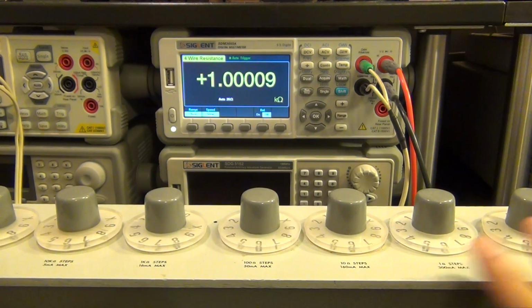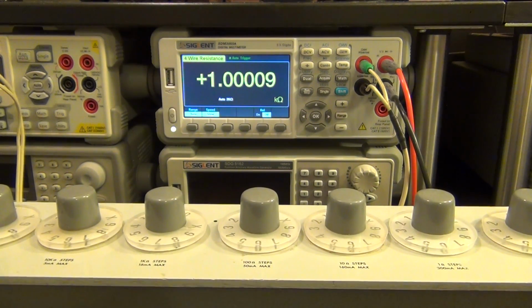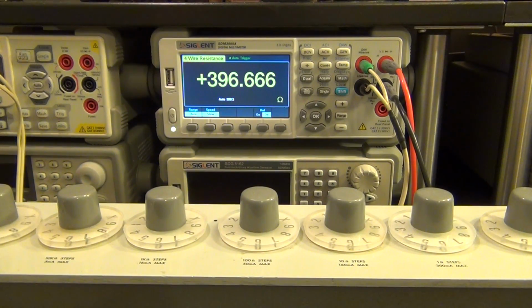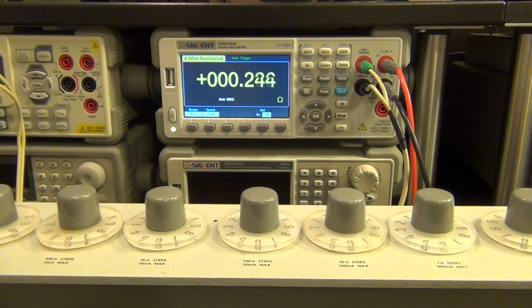When I said this resistor box isn't very accurate, I was talking about its lowest range. If I use the 0.1 ohm steps and go up by 0.1 ohm, you can see it does kind of go by 0.1 ohm. It's not exact, but fairly close, because the contact resistance needs to be cleaned. Here's another 0.1 — it's not so bad.